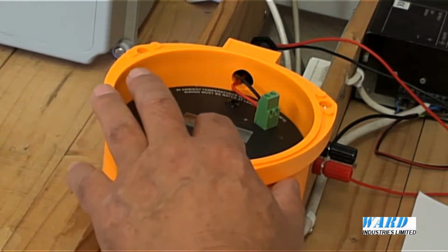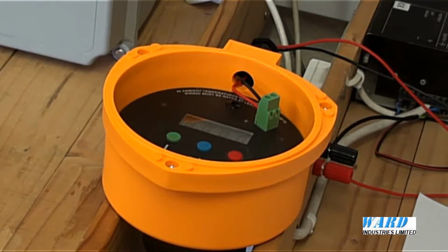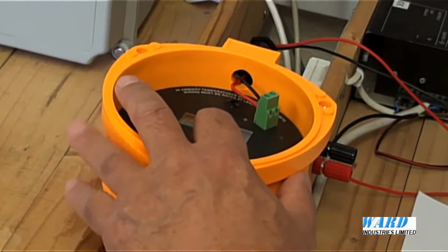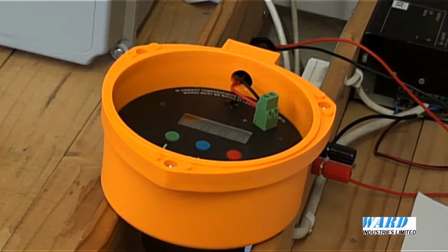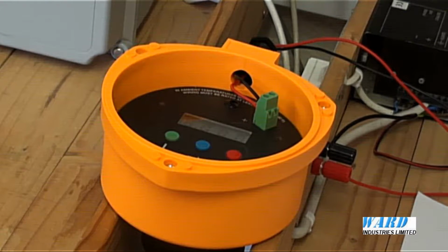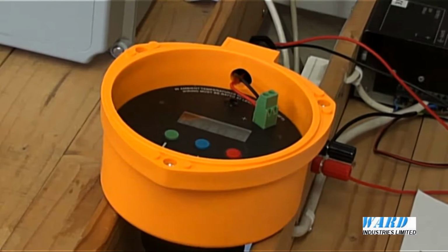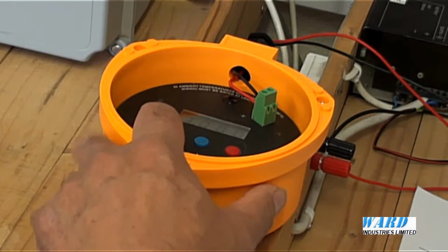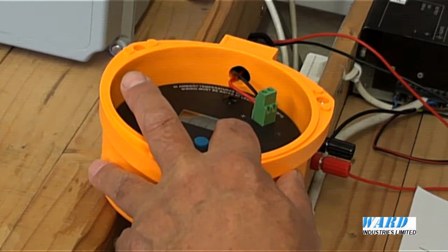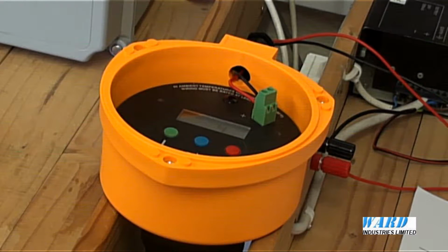So we've used the green button to select Bref. Now press the blue button. This shows the current value of bottom reference. Press the blue button again and the first digit starts to flash. This means that we can start editing. Use the green button to change that to 1. Now move along using the blue button until we come to the end. Press the red button to accept it, and the bottom reference value has now changed from 8 meters to 1 meter.